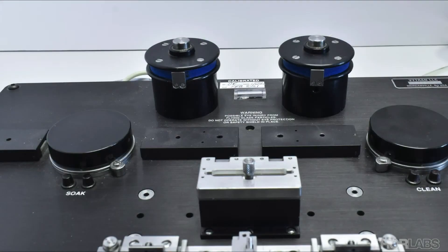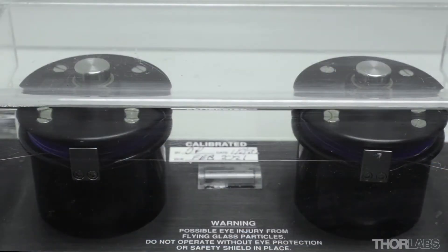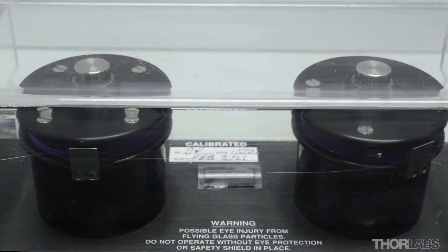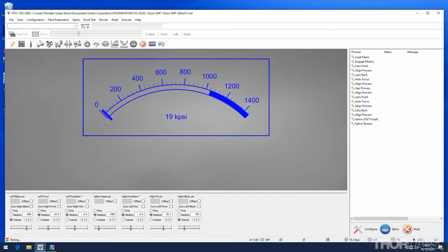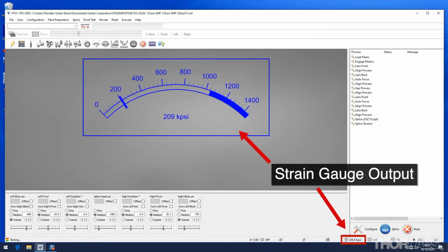The proof tester consists of two mandrels onto which the fibre is wound. The left mandrel remains stationary. The right mandrel rotates and applies an increasing load to the fibre which is measured by a strain gauge. The applied force is reported to the software.